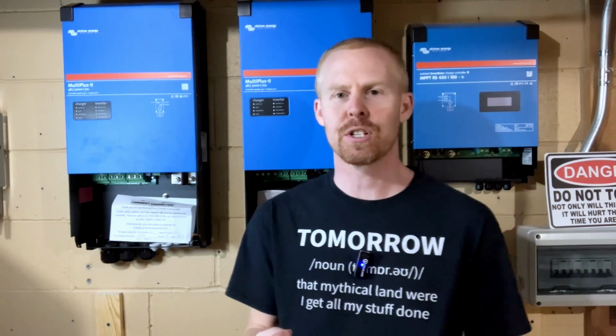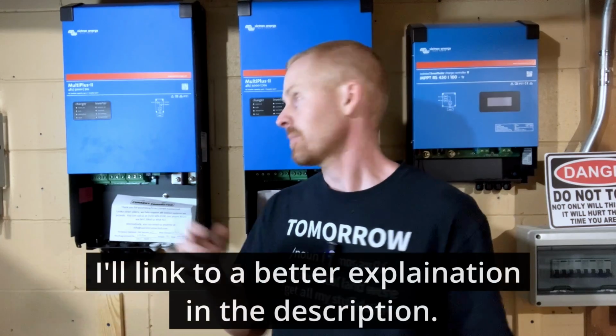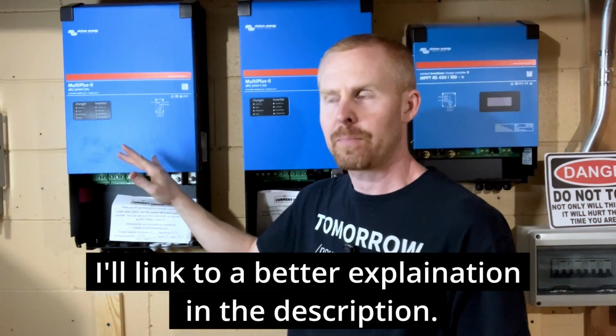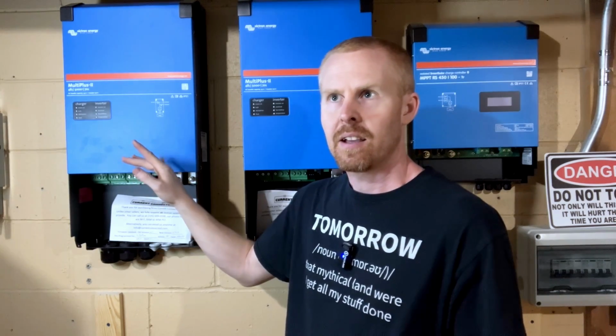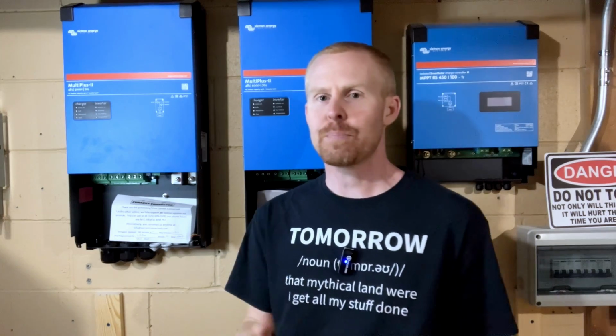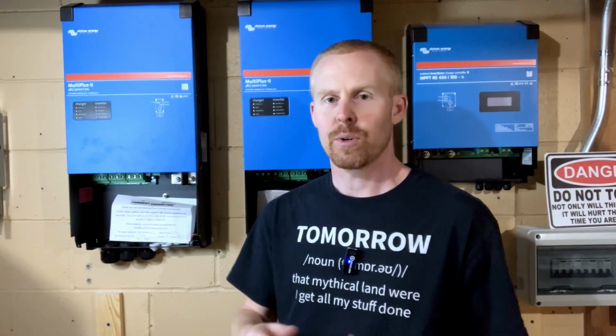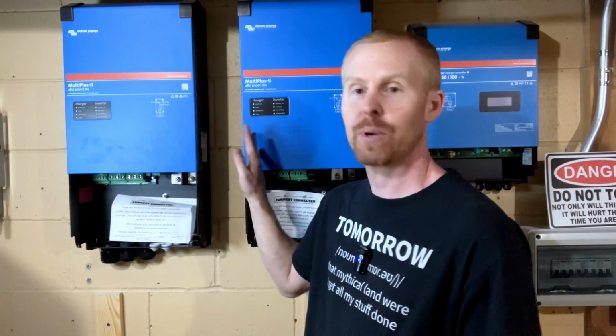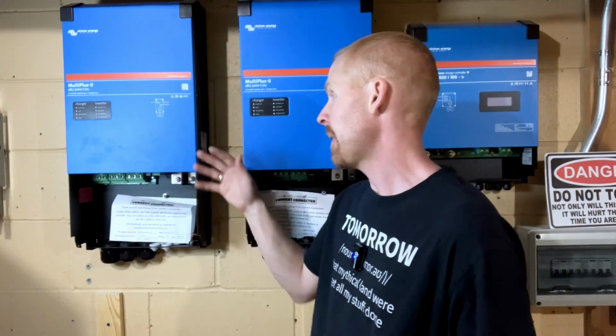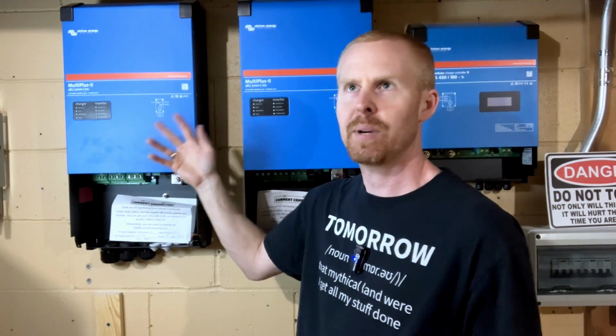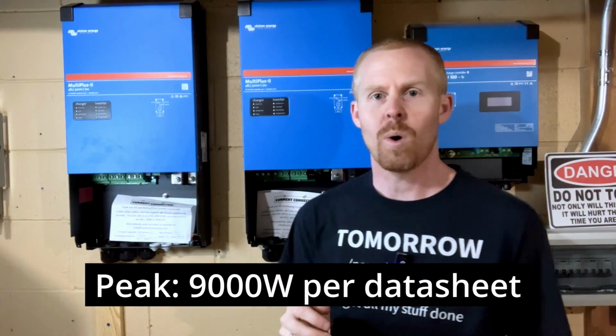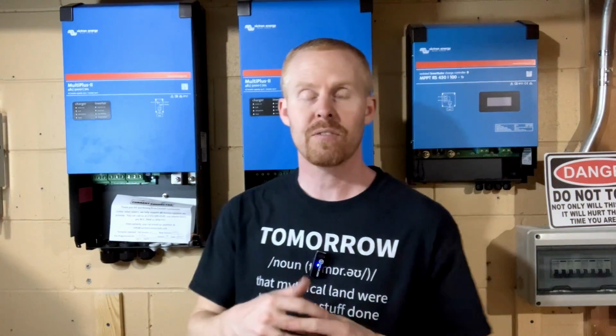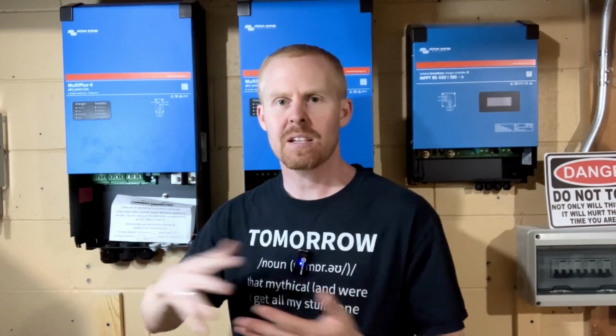I still don't have a very good grasp on it, but they rate these units at 5,000 VA, and then they derate to 80% power factor for a standard output. So the standard output on these is 4,000 watts, assuming you're using inductive loads and that kind of stuff. And then the surge, or peak, it might be peak, is 9,000 watts. So with these being only 4,000 watt units, between the two, I've got 8,000 watts of potential power with the peak and the surge.